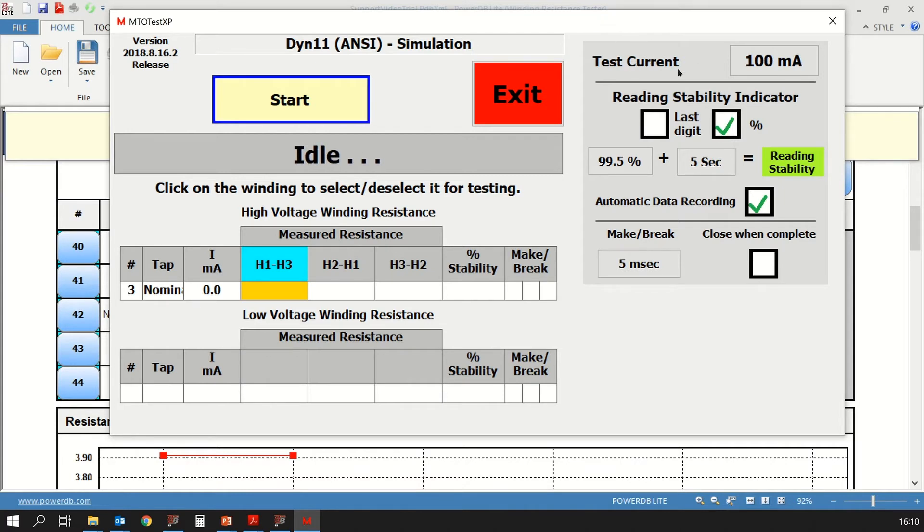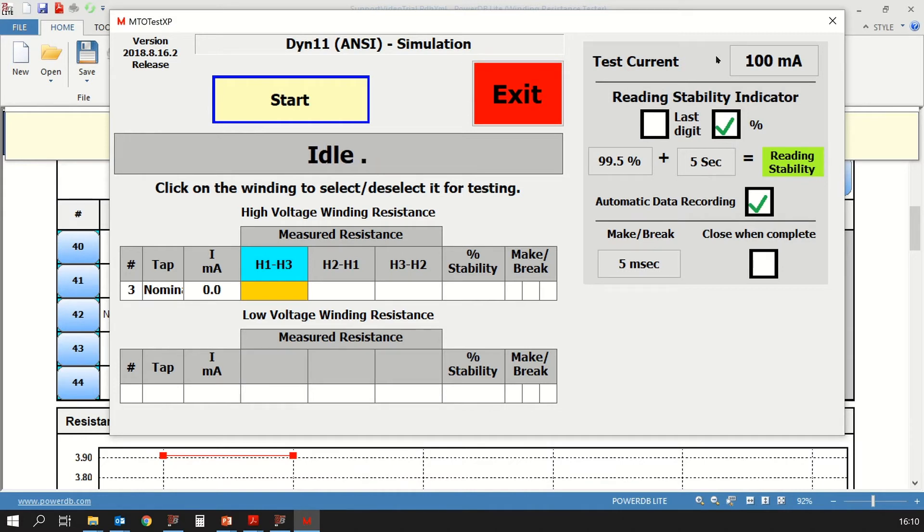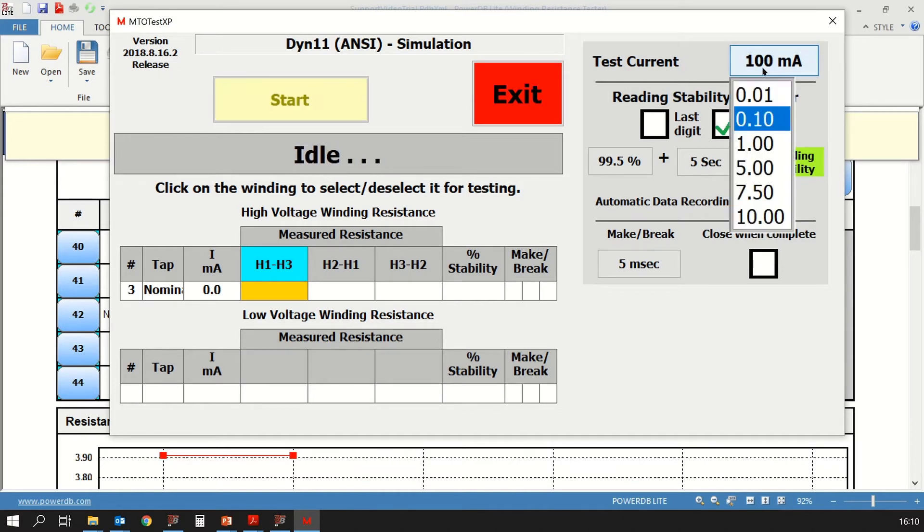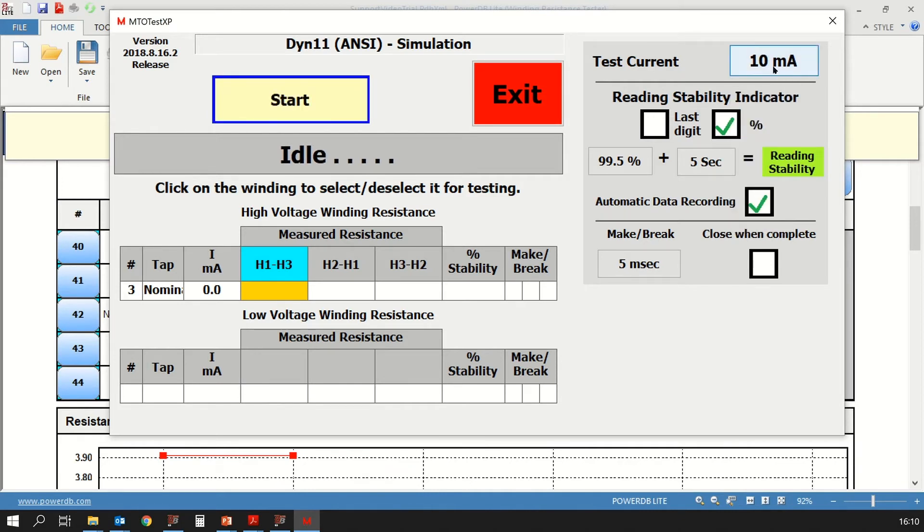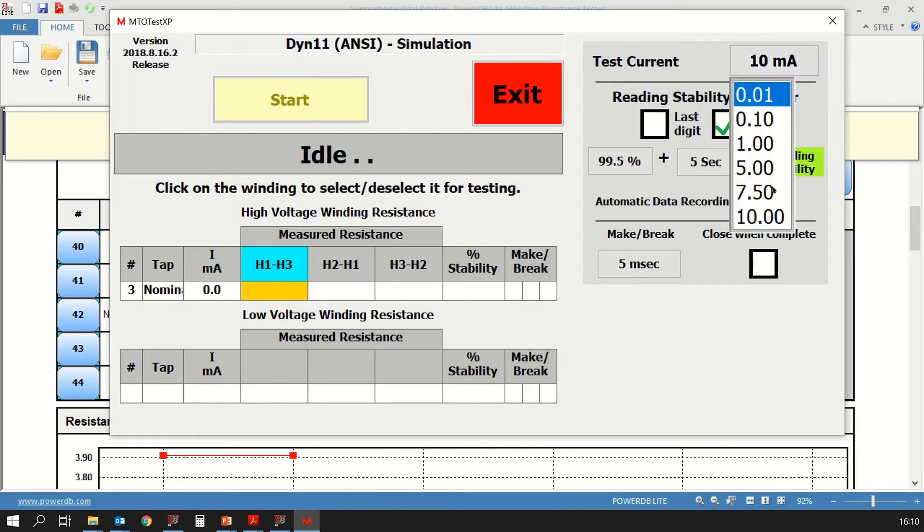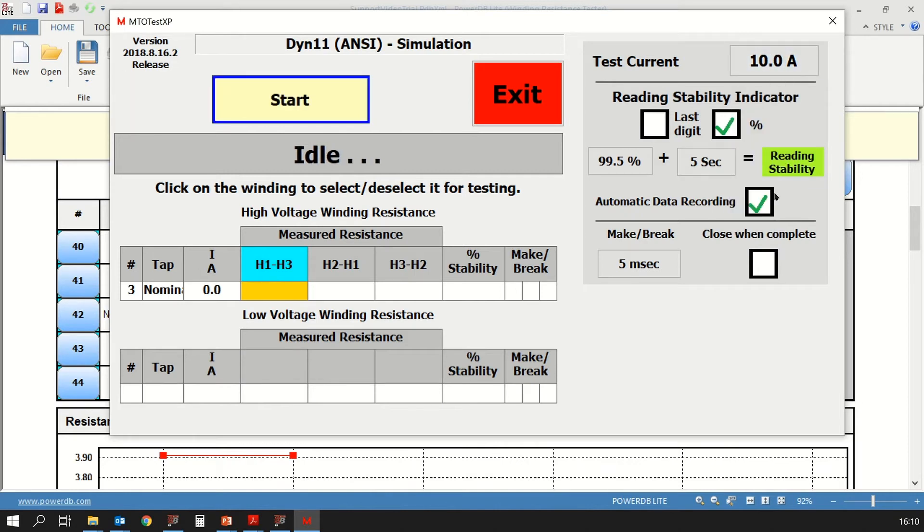Now let's look on the right side of this dialog box. First you will see the test current. That will be the DC test current that will be applied to the transformer to make a measurement. This current is configurable, and you can select it based on the transformer you're testing. You have several options, 10 milliamps all the way up to 10 amps. We are going to select 10 amps in our case.